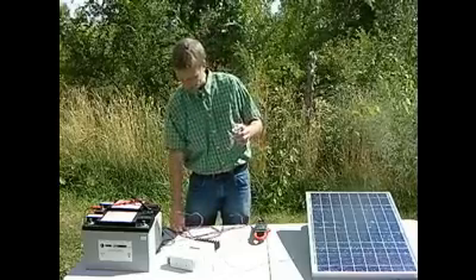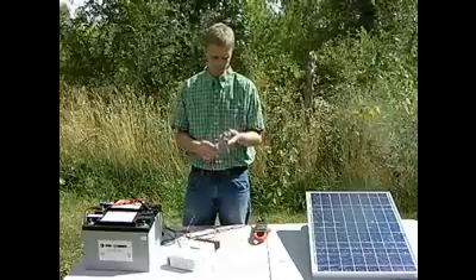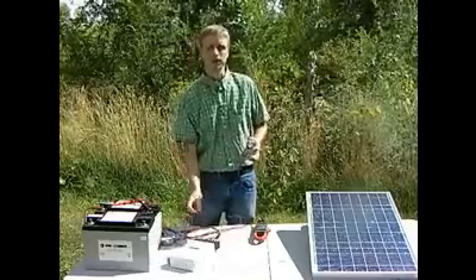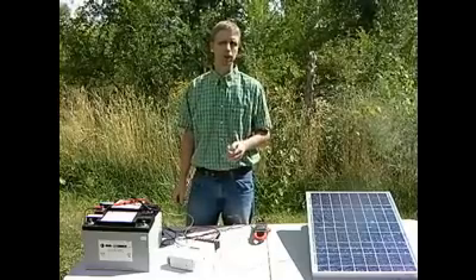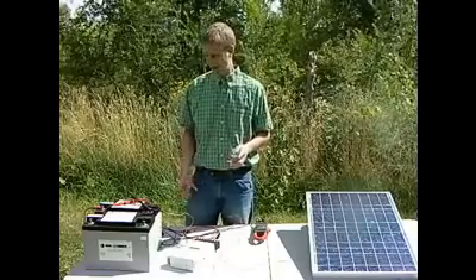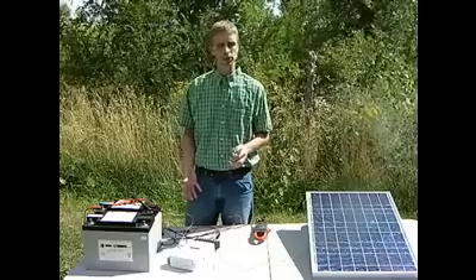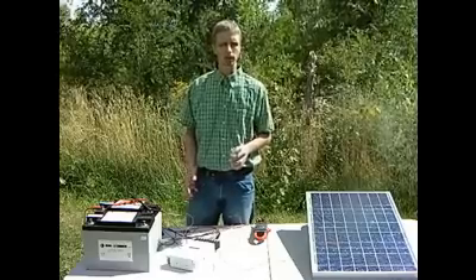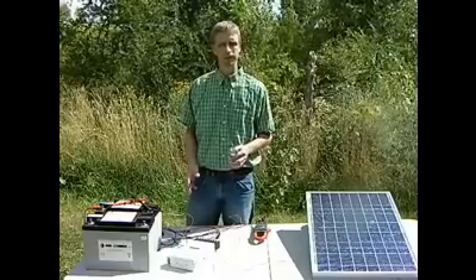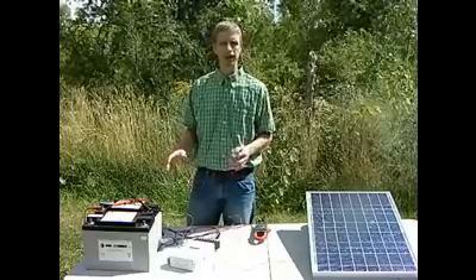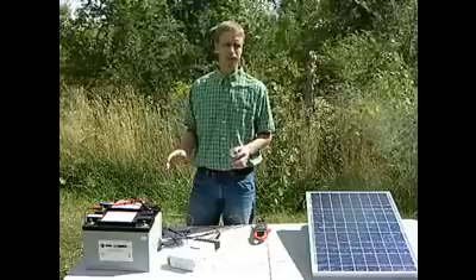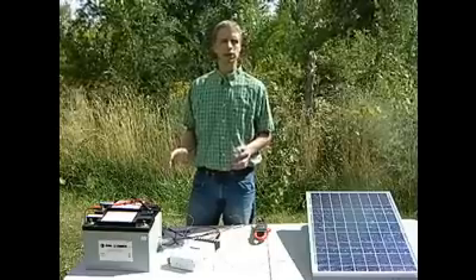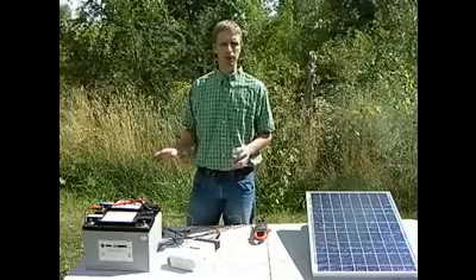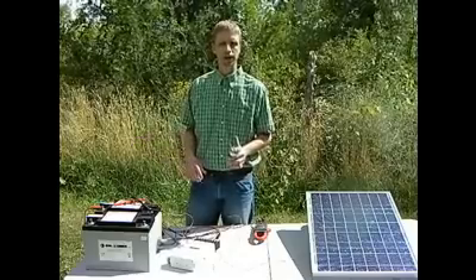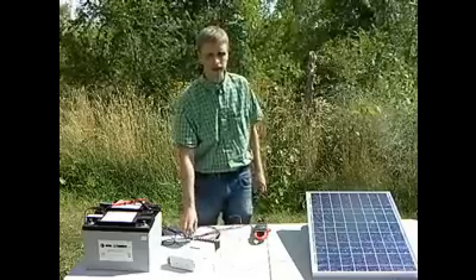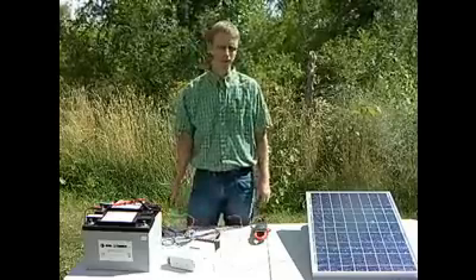We'll disconnect that so we don't have another short circuit. So once again, remember, on your loads you want to use a fuse or circuit breaker if possible to protect the wires. Just as in the case we had here, if you have a short circuit in your wires and don't know about it, instead of your wires getting hot, melting, and possibly starting a fire, the fuse or circuit breaker will just trip and blow, and everything will be okay. It's essentially a way of protecting your wires and yourself from getting too hot.